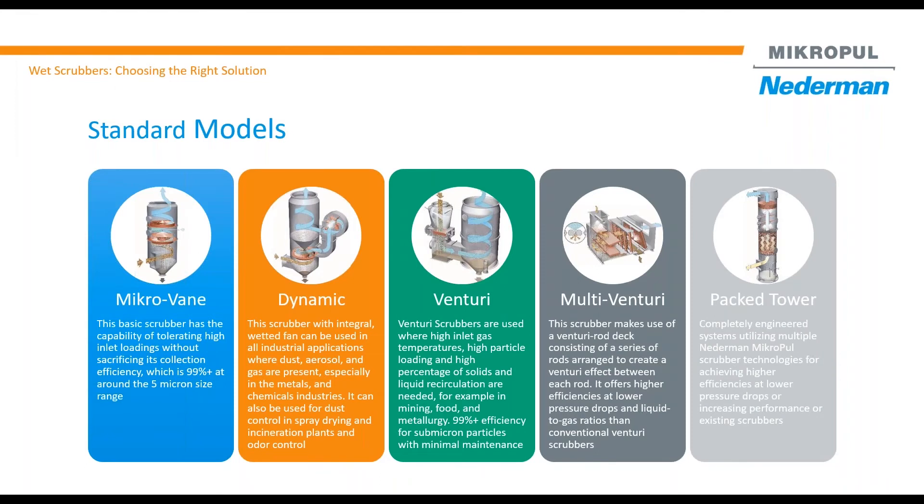MikroPul has developed over the years many different standard models, but we always come up with something different from our standard. MicroVane is a basic scrubber design. It is the most compact and has been used for many dedusting applications and other applications where your particles are 5 micron or larger. MicroVane is a pretty easy scrubber — it operates around 3 to 6 inch pressure drop and liquid to gas ratio is about 2 to 4.